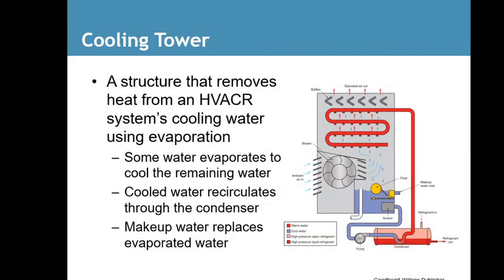Cooling tower, a structure that removes heat from an HVAC-R system. Cooling water is used for evaporation. Some water evaporates to cool the remaining water. Cooler water circulates through the condenser. Makeup water replaces the evaporative water. And again, on this picture, just to show you again, there's this little bottom right-hand corner blue box that has the yellow float and valve in it. That's something that is constantly adding water. Whenever the water drains down, it adds more. So it's an automatic fill system.